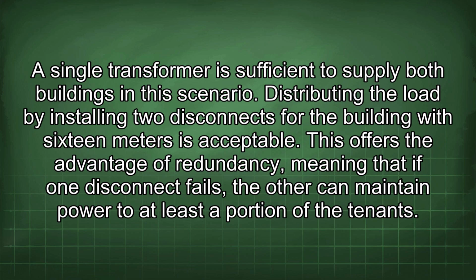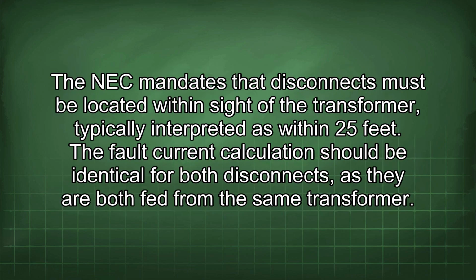Distributing the load by installing two disconnects for the building with 16 meters is acceptable. This offers the advantage of redundancy, meaning that if one disconnect fails, the other can maintain power to at least a portion of the tenant. The NEC mandates that disconnects must be located within sight of the transformer, typically interpreted as within 25 feet. Fault current calculation should be identical for both disconnects, as they are both fed from the same transformer.